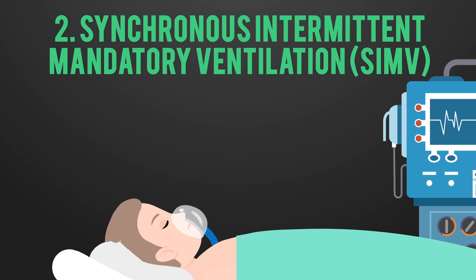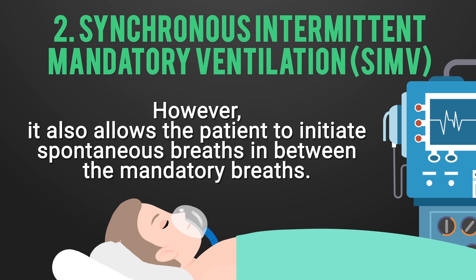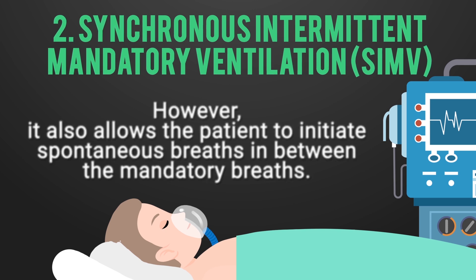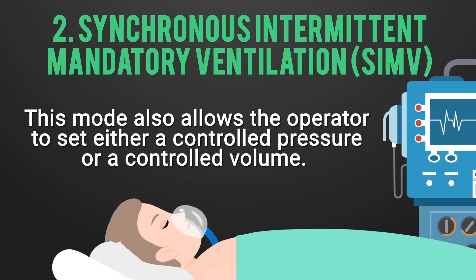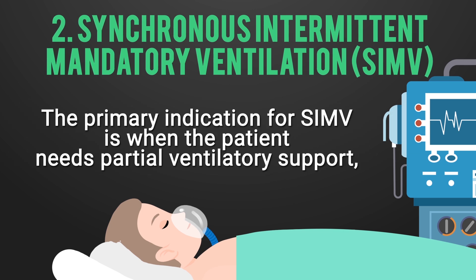The second primary mode is SIMV, or Synchronous Intermittent Mandatory Ventilation. In this mode, the ventilator delivers a preset minimum number of mandatory breaths, but it also allows the patient to initiate spontaneous breaths in between the mandatory breaths. This mode allows the operator — either the respiratory therapist or the doctor — to set either a controlled pressure or a controlled volume.